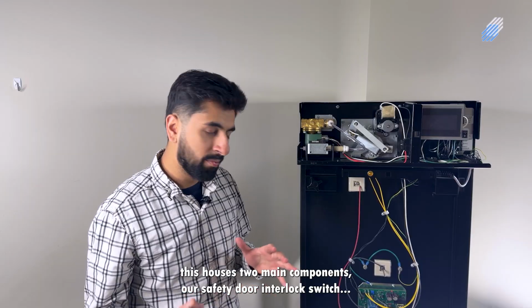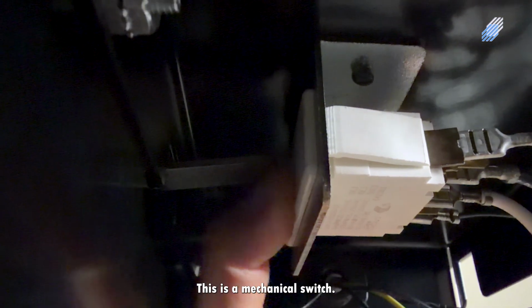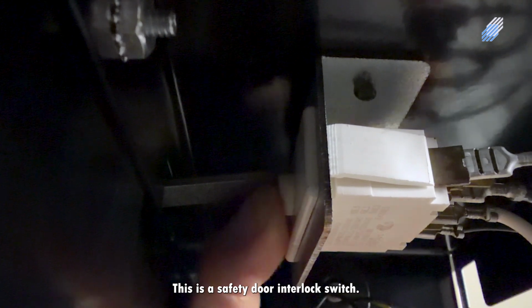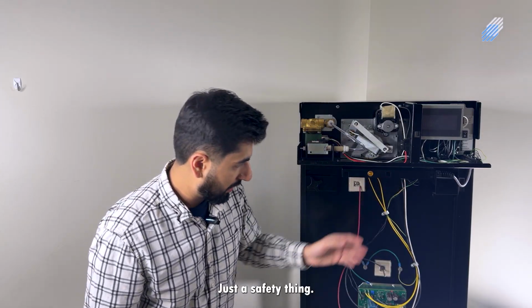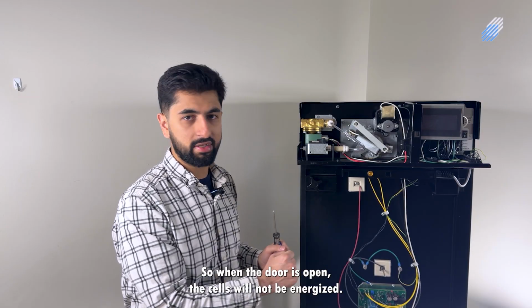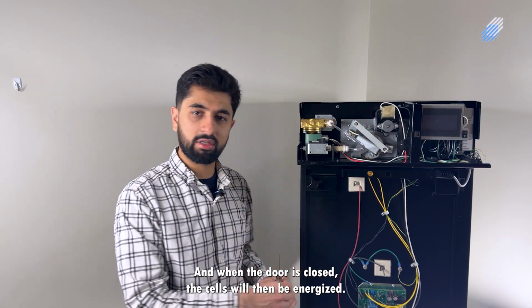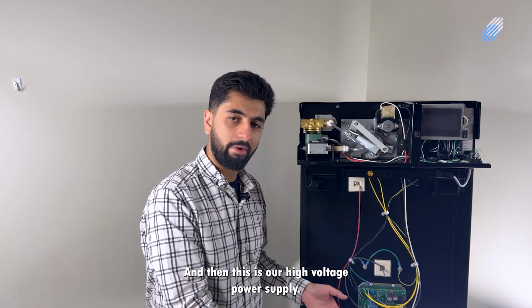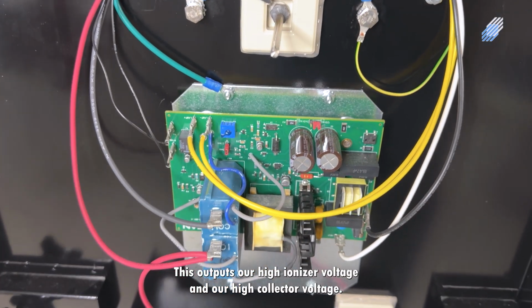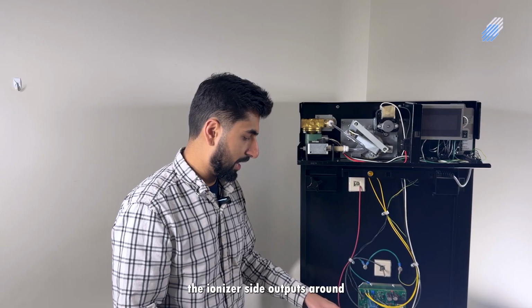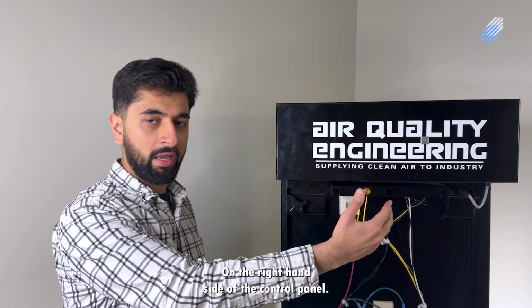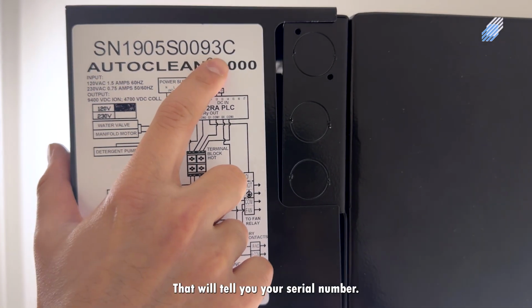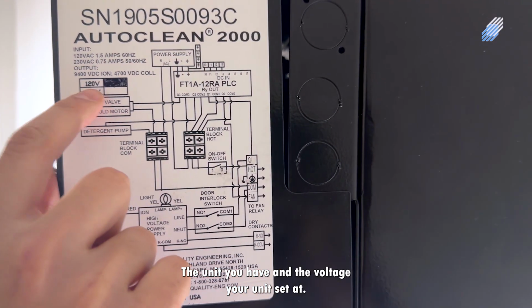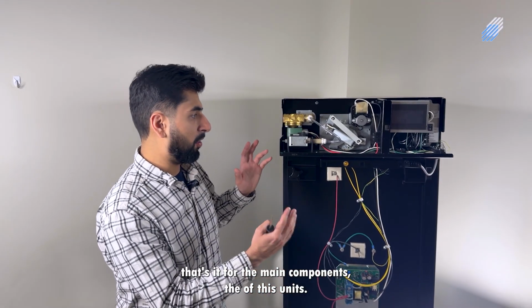This houses two main components. Our safety door interlock switch. This is a mechanical switch. It's a mechanical spring-loaded switch. Just a safety thing, so when the door is open, the cells will not be energized. And when the door is closed, the cells will then be energized. And then this is our high voltage power supply. This outputs our high ionizer voltage and our high collector voltage. The ionizer side outputs around 9.4 kilovolts DC, and our collector side outputs around 4.5 kilovolts DC. On the right-hand side of the control panel is your schematic. That will tell you your serial number, the unit you have, and the voltage your unit is set at. So that's it for the main components of this unit.